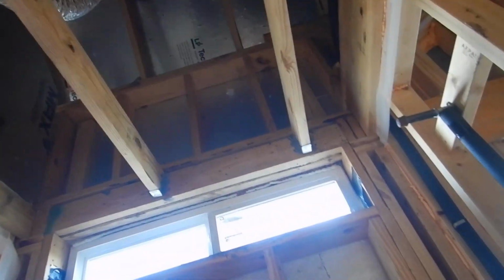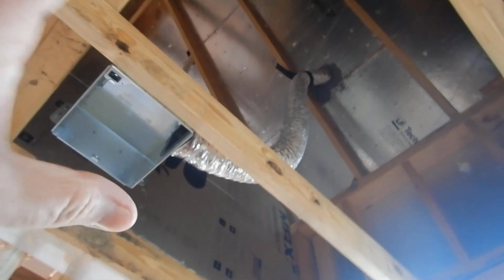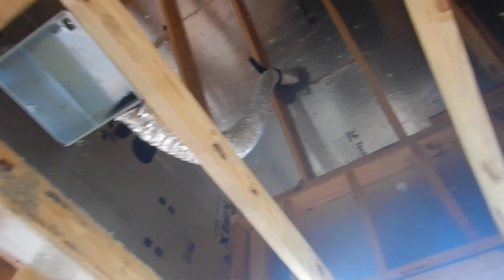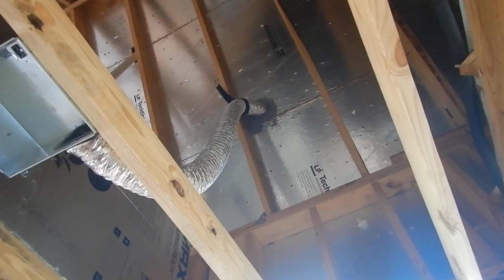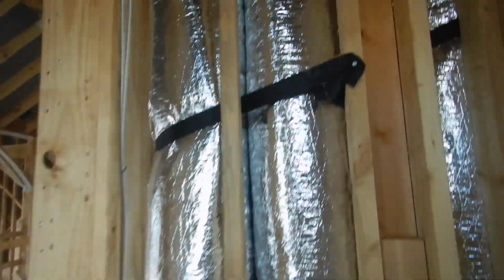When I shoot this with an infrared camera, when I come back and inspect this house and I'm waving an infrared camera around here, these are all going to be glowing hot, bringing the radiant heat in because, in part, these were not insulated. Air duct touching air duct.